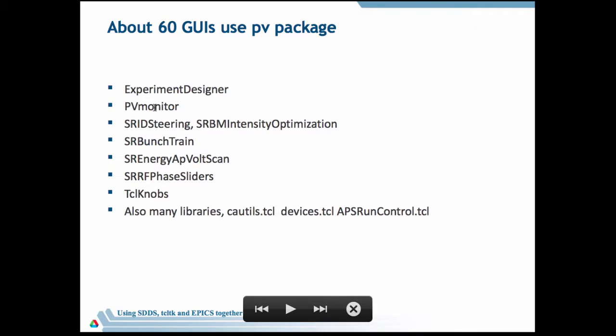PV Monitor allows you to set, we have that for the radiation monitors in the control room. If a radiation monitor, of which you have about 35, exceeds some value, say the minor alarm, then you want to stop injection by ourselves rather than using the ASIS system. So the PV monitor could be configured to do something as a result of a value changing. This was actually the idea of Steve Christensen. He proposed that and we created it in a day.